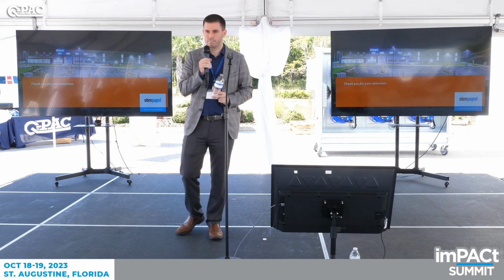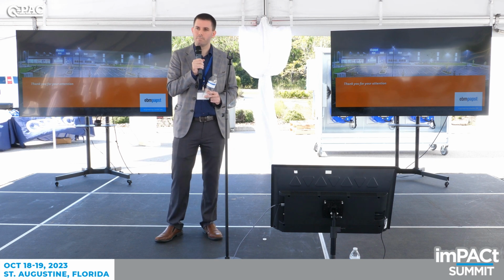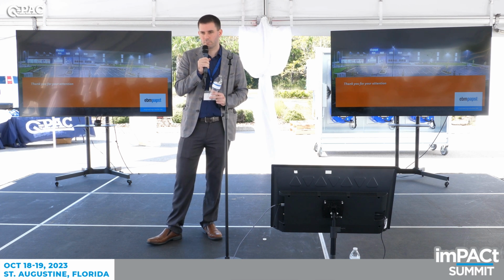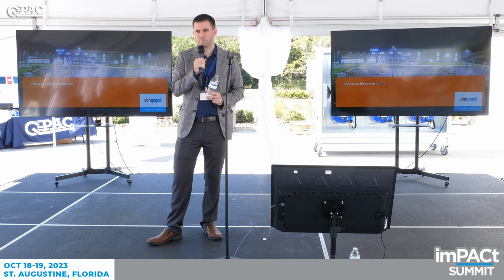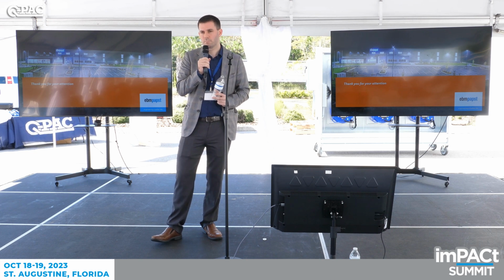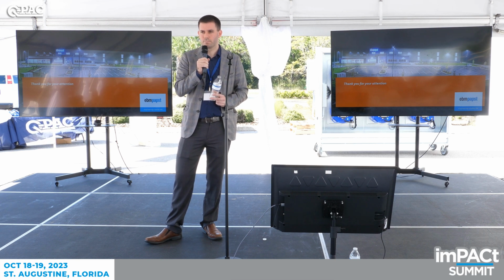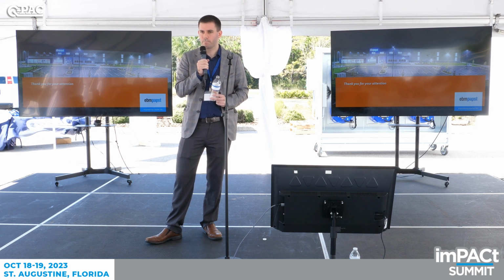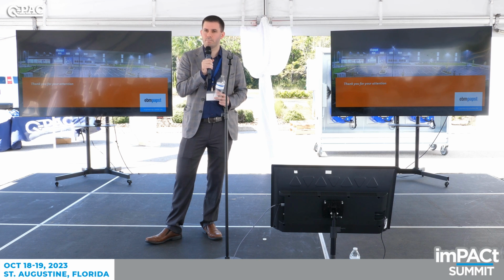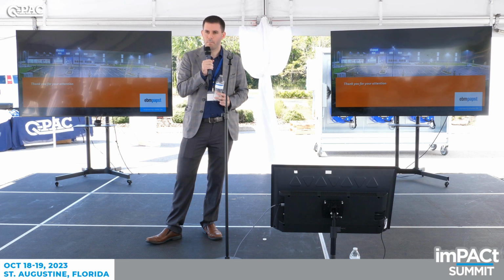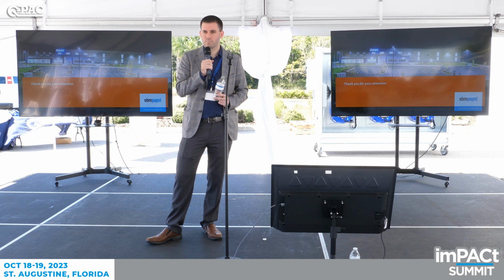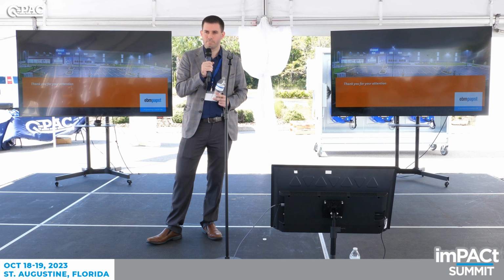I just want to comment on the living life of these fans. They live in a saturated environment, and here in Florida, what we've noticed over time is that those fan arrays will develop a black growth, on the wheel, motor, electronics, pretty much anything that's saturated in that environment. It's a little unsightly. We're not really sure what it is. We've never had it analyzed, but it appears to be some sort of black microbial growth. We've seen that happen over and over again, especially on Q-PAC arrays that are older than 5 years. So if you ever see it, that's what's happening: it's operating in that saturated environment for a long time. And it's dark, and it's wet, and it's cold. So just understand that can happen.